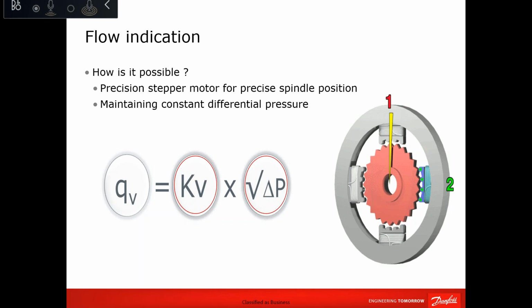Assuming that across the valve there is the minimum differential pressure, every single position is detectable. If we take an example of 2.5 millimeter and divide it by 1024, 0.0025 millimeter is the movement. That precision will give you on its own, without the interference of pressure, about 2.5% error. But if you put the pressure on, then it will be 5 to 10% accuracy. Overall, the flow indication from the Novocon, assuming you have enough pressure across the valve, is 5 plus or minus 5% accuracy.